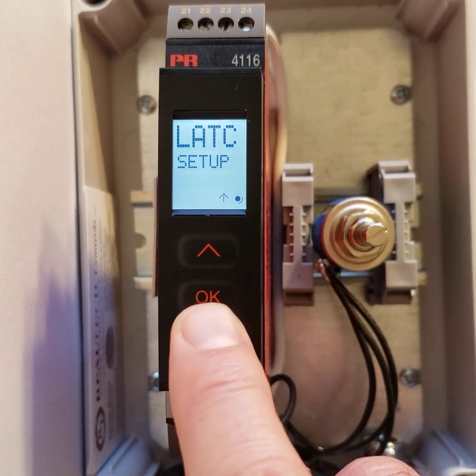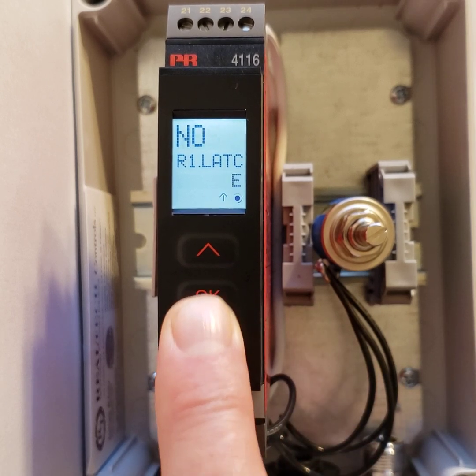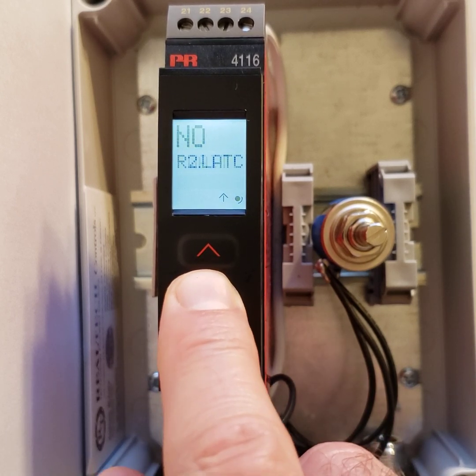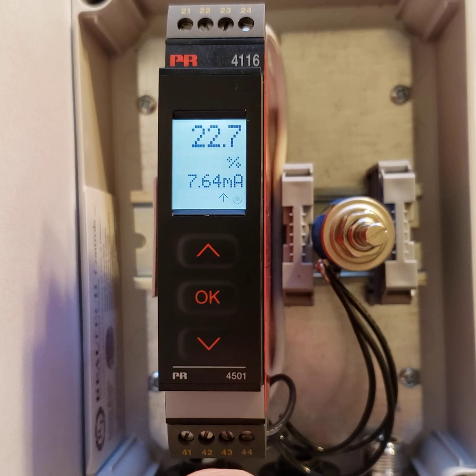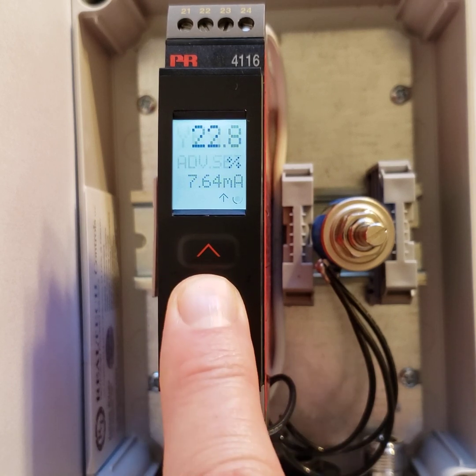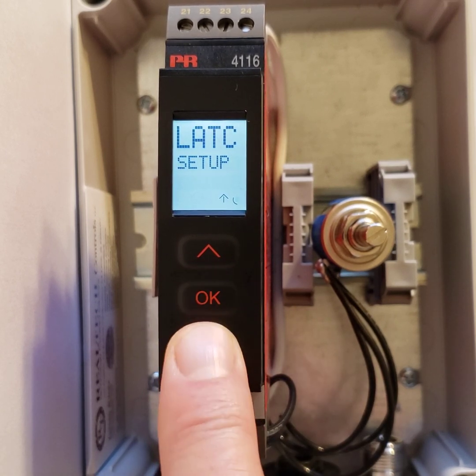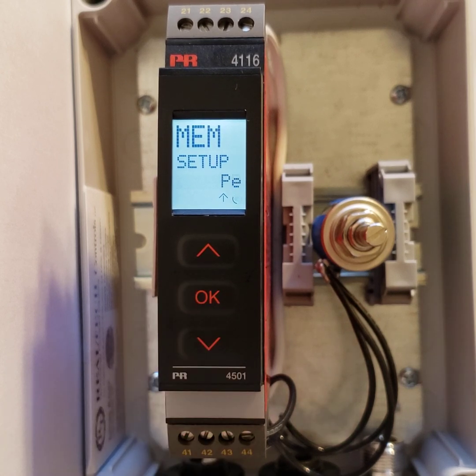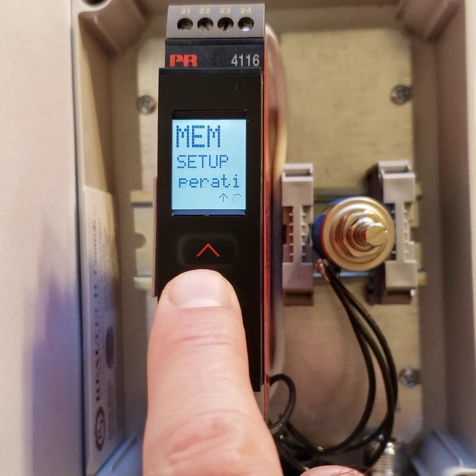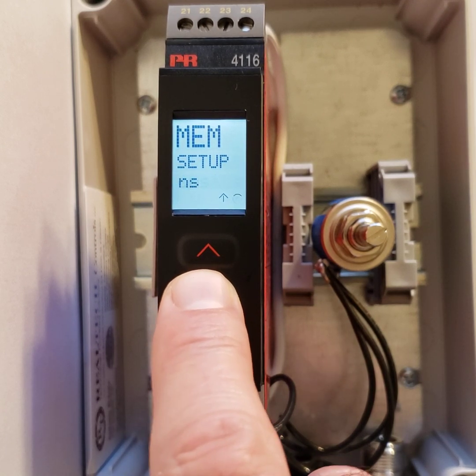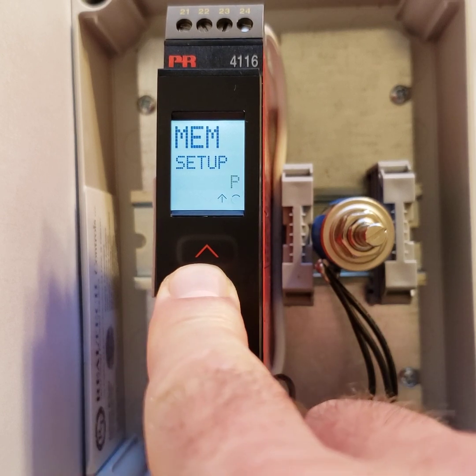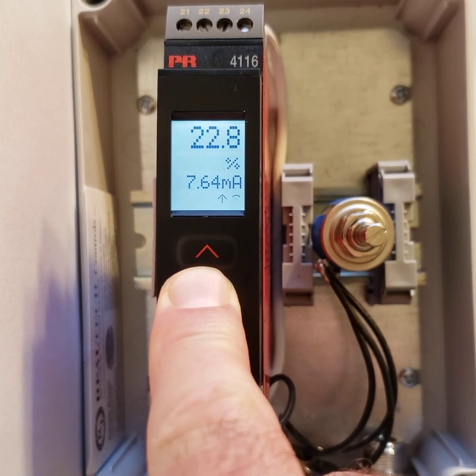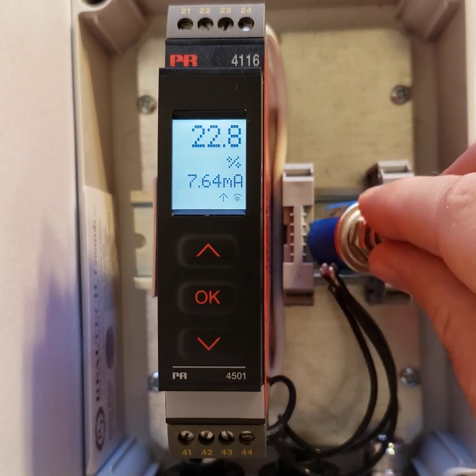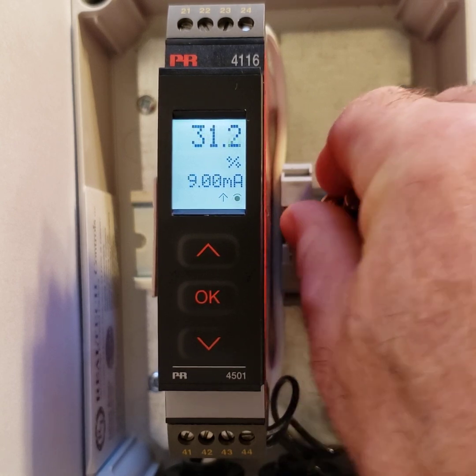So I'm going to get in there. I'm just going to set my latch. I'm going to take that latch off. There we go. If we go into the advanced menu again, it just scrolls back to memory again to cycle through that menu structure. That is the programming of the advanced menu of the 4116 transmitter. Remember, holding the OK button gets you out of there. And then this is just my normal operating and my process again.